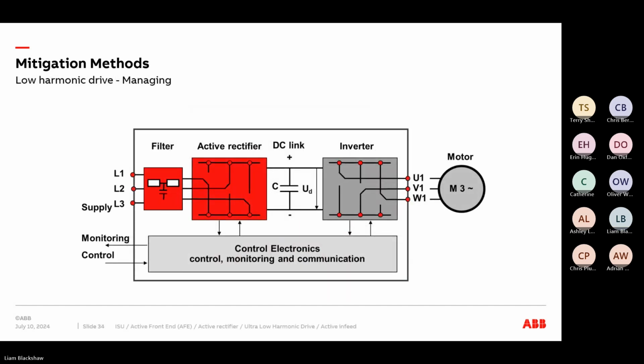Another one is how we look at harmonics, and this is again drive related, so I do apologize, because I wanted to generalize this about harmonics in general. But if we look at it from a drive's perspective, in some cases, instead of using a 6-pulse drive, you might want to use what we call a low harmonic drive that allows us to manage harmonics on a system. You may have heard terms like active in-feed, active rectifier, active front end, or ultra low harmonic drive, and that's what they are. It's a low harmonic drive that manages harmonic content, and instead of having diodes on the input, you'll have IGBTs that switch on and off accordingly. They act as switches basically to control those levels of harmonics.